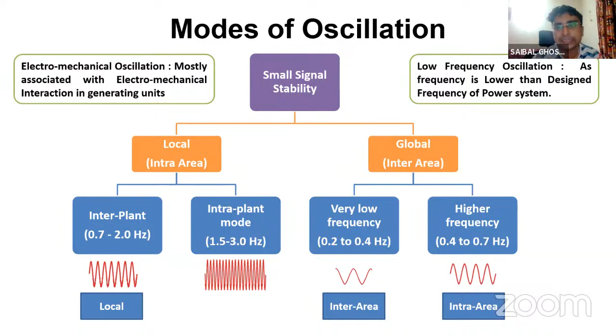So this oscillation frequency is higher, whereas inter-area oscillation is very low frequency, in the range of 0.2 to 0.4 hertz. Also, some small areas can be formed, which we call intra-area, meaning nearby generators can form a group and oscillate against each other. That comes under this category.